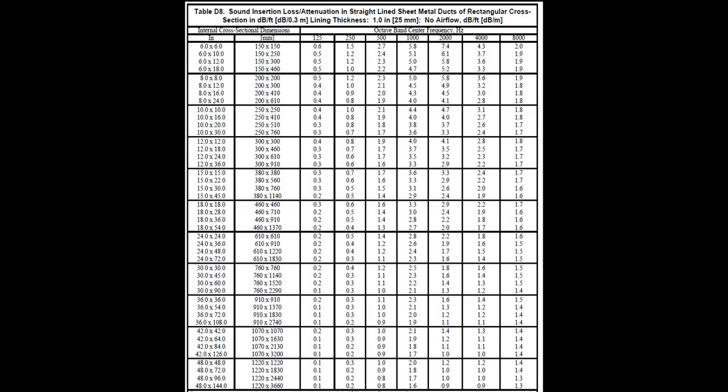Now let's move on to path 2. We add sound insertion attenuation and duct transmission loss factors for this particular path. This sound insertion attenuation is covered under D1.3.2 in Standard 885. For this example, let's assume this is 5 feet of lined rectangular duct with a cross section of 12 by 12 with 1 inch fiberglass liner. Please note that the values in this table are by the foot, so to find the overall you must multiply by the full length of the duct.